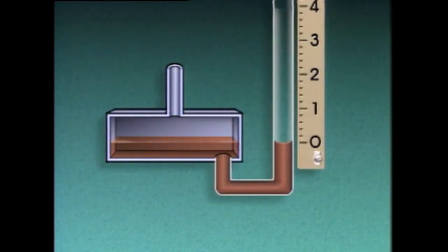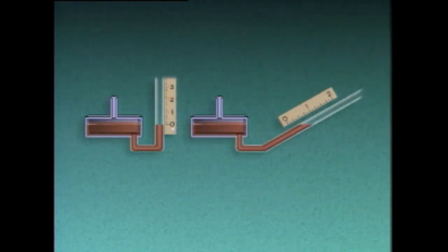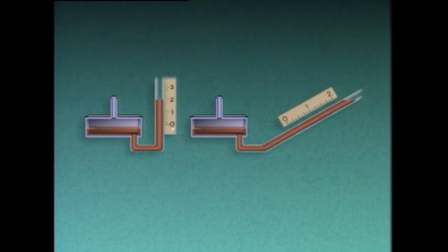Two other types of manometers used in industry are the well manometer and the inclined manometer. Both work on the same basic principle as a U-tube manometer, but they're read differently. Rather than adding the levels in two legs, both a well manometer and an inclined manometer are read directly from the top of a single column of liquid. With any type of manometer, the level of the liquid indicates the pressure. Different liquids can be used in manometers, and some liquids are read differently than others, so you have to know how to read the liquid level correctly.